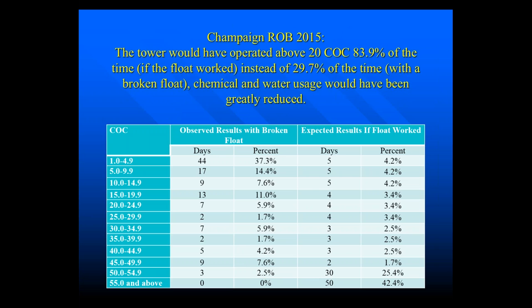The cycles of concentration ranged from 1.4 all the way up to 55 and above. This shows what we observed with a broken float — how many days we were at each cycle of concentration. It never got above 55 cycles of concentration and was above 50 only three days. If the tower had operated the way we expected, I estimated it would cycle up and stay at high cycles of concentration. The tower would have cycled above 20 cycles, 84% of the time if the float had worked — instead, it was more like 30% of the time.